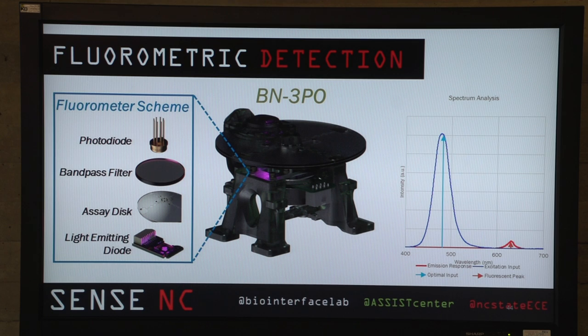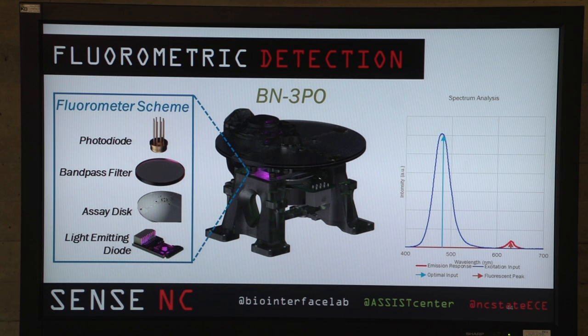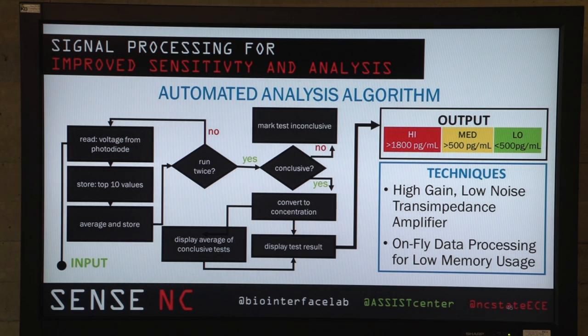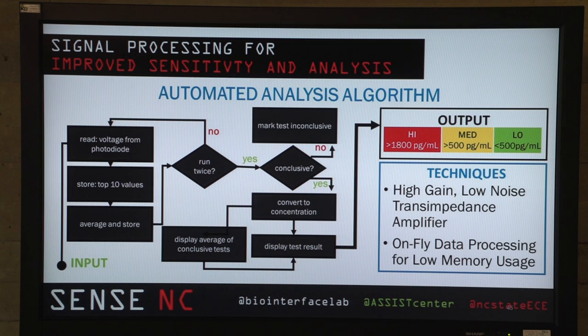In terms of detection, once we have everything in the right well and the microfluidic channels have flowed, how do we determine the amount of BNP present? We use a light emitting diode to shoot light at the latex beads. Those beads are excited and the light is passed through a filter, which filters out the excitation light and allows through only the light from the fluorescent molecules. This light is received by a photodiode, which translates that signal to a voltage. You can see our spectrum analysis on the side. The device analyzes the sample and gives a response in concentration, binned into high risk, medium risk, and low risk. There's no need to send results to a professional — it's displayed so a user can see the results instantly.